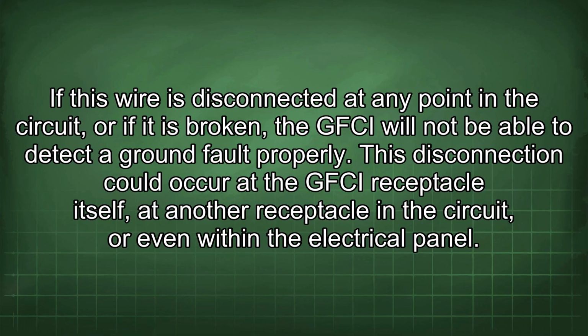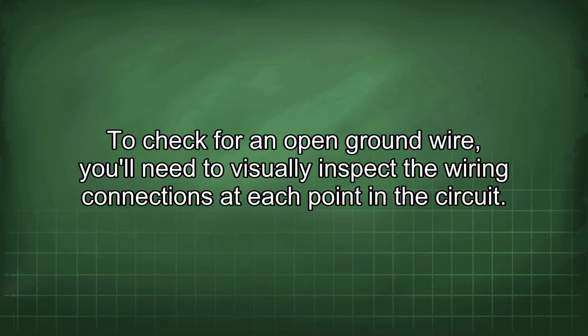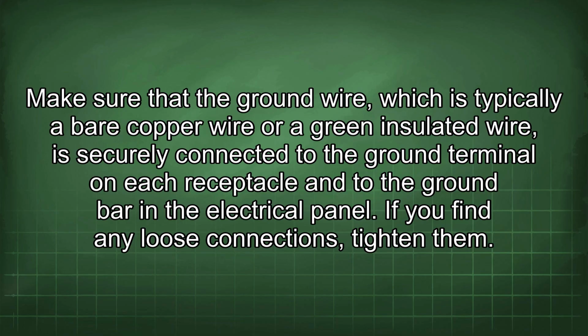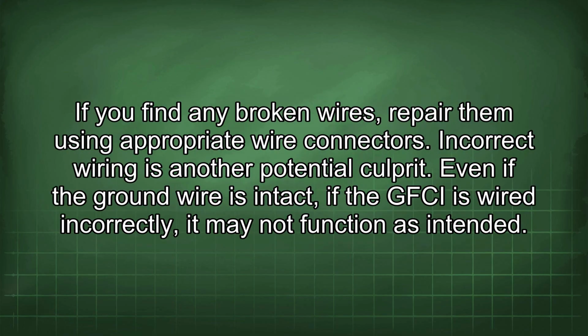This disconnection could occur at the GFCI receptacle itself, at another receptacle in the circuit, or even within the electrical panel. To check for an open ground wire, you'll need to visually inspect the wiring connections at each point in the circuit. Make sure that the ground wire, which is typically a bare copper wire or a green insulated wire, is securely connected to the ground terminal on each receptacle and to the ground bar in the electrical panel. If you find any loose connections, tighten them. If you find any broken wires, repair them using appropriate wire connectors.